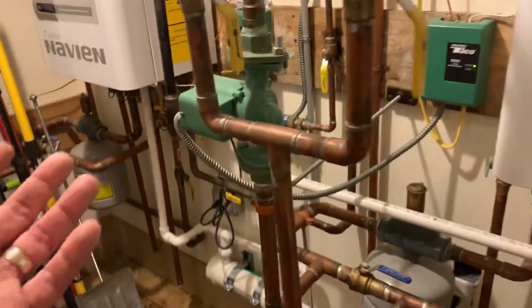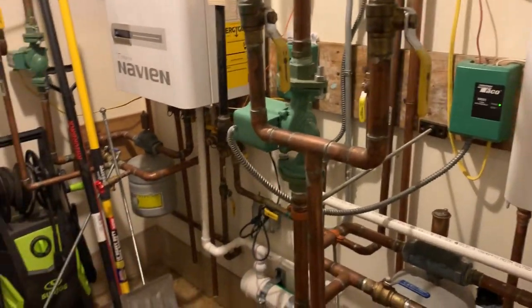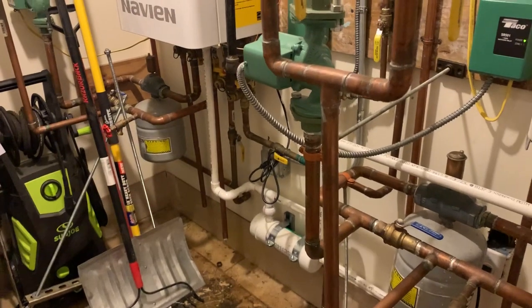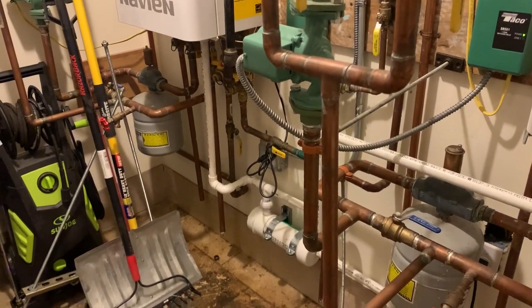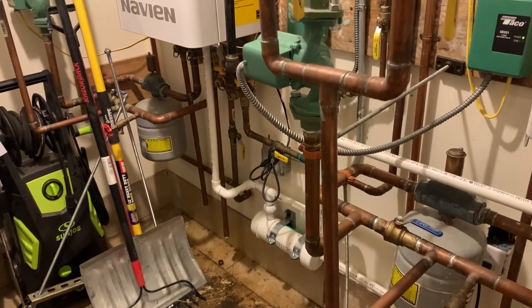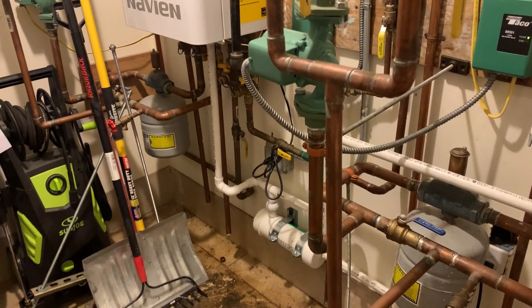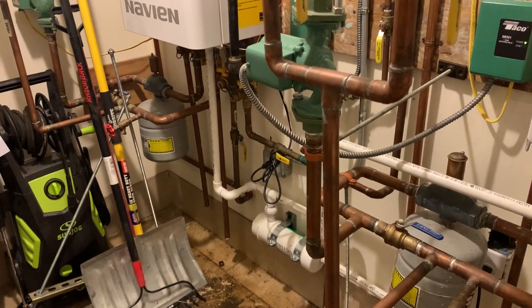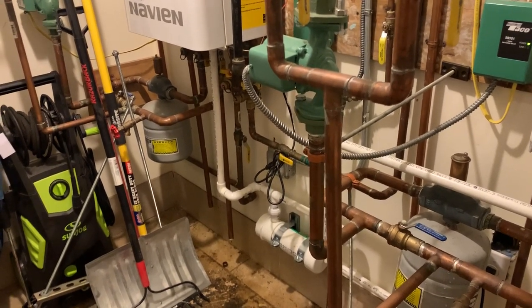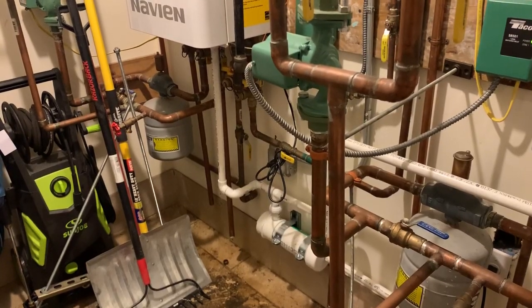You know, I'm on a service call to do a tune-up, flushed out both of them, added a neutralizer, doing my best. You know, again, I'm not trying to reinvent the wheel here, but I'm also not trying to bang the client in the head for an exorbitant amount of money, looking for a drain stack, cutting in a T with a trap, a standpipe. I'm not trying to reinvent the wheel here, so that works for me.